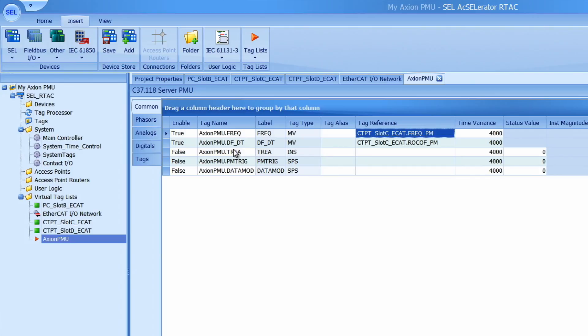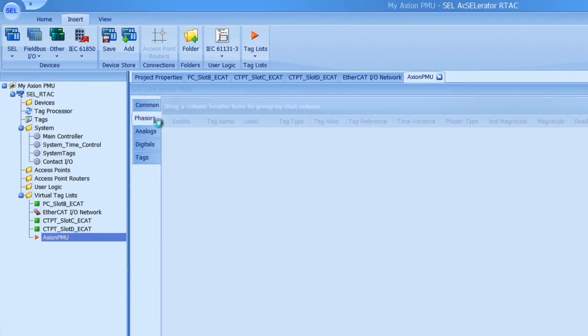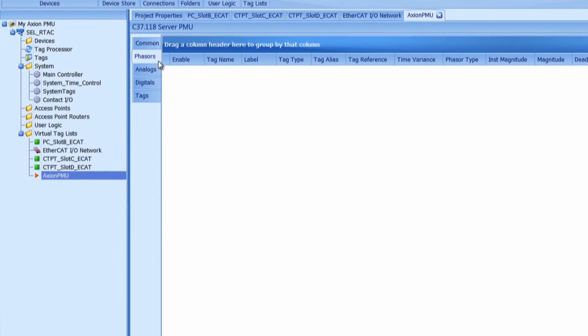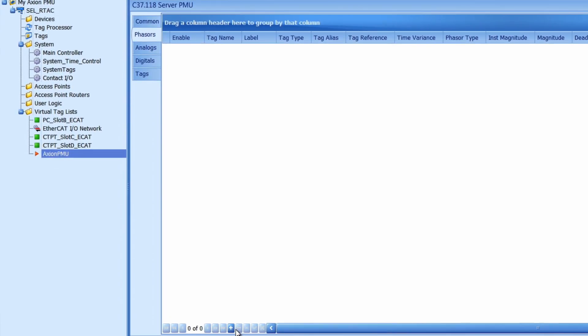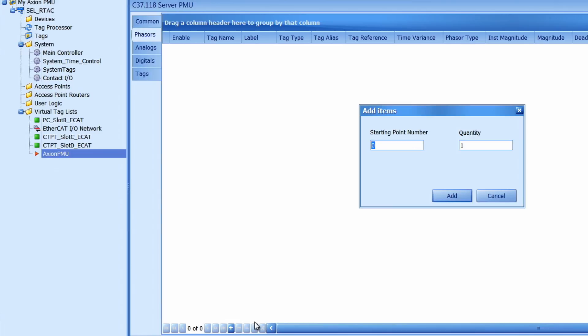Now let's add in our phasor quantities into the tag map. Go to the phasors tab here and click on the add button down here. Enter the number of phasors that you want to add. In this case I have two CTPT modules with 14 phasors each. So I'm going to add 28 phasors to my tag list. And then I'll select add.